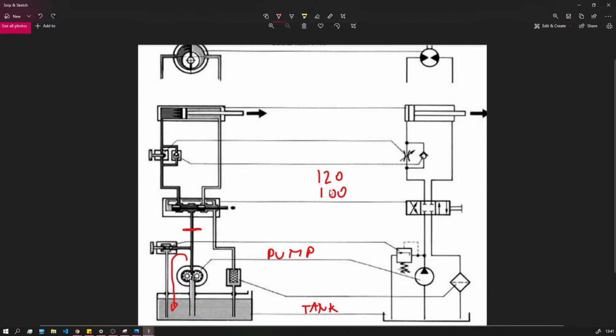So the lowest pressure setting wins. The distribution system can be at higher levels of pressure, and the machine can be operating at lower levels of pressure. It's kind of regulating the output pressure.